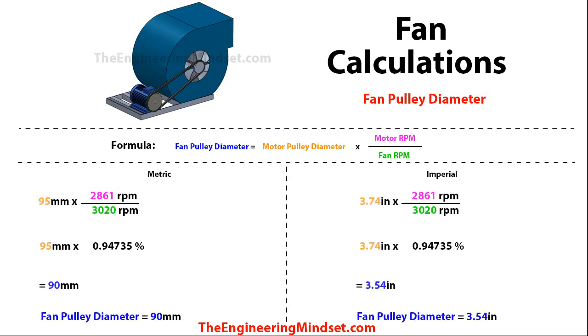The first calculation is the fan pulley diameter. The screen is split into metric and imperial calculations. The formula is: fan pulley diameter = motor pulley diameter × (motor RPM ÷ fan RPM). We have some data in the calculations here — you can get these figures from the manufacturer, or look them up online if you haven't already purchased the equipment.